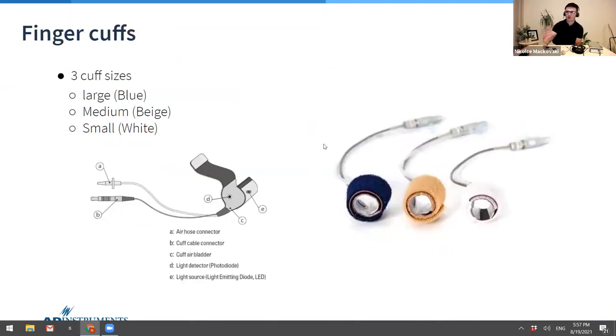The finger cuffs are probably the most important part of this NIBP unit itself. They come in three different sizes: blue for large, beige for medium, and white for small. They comprise a Lemo connection that goes to the NIBP wrist unit and also an air hose. This air hose then connects to the air bladder that's inside the cuff. You can see here the air bladder in these cuffs, and we also have the Velcro strap around.